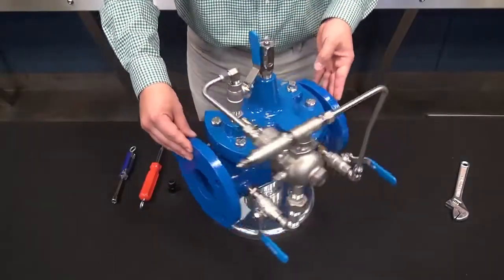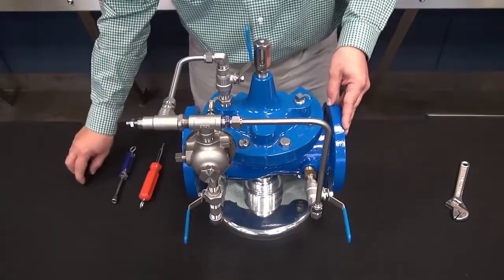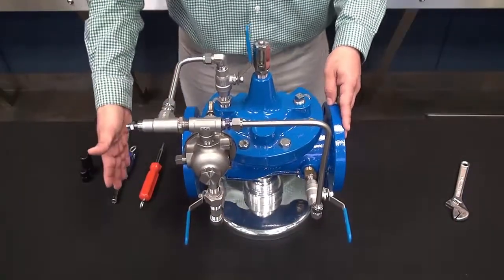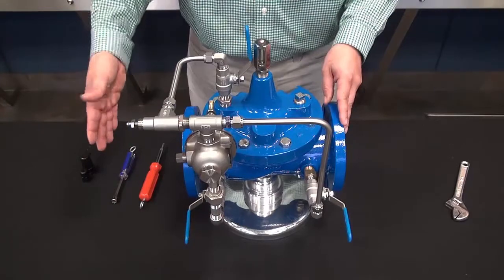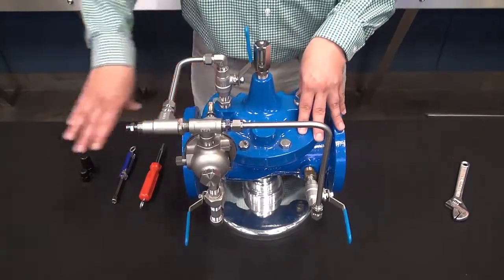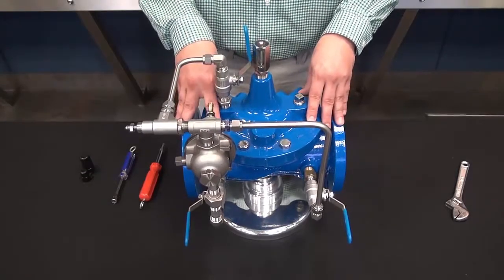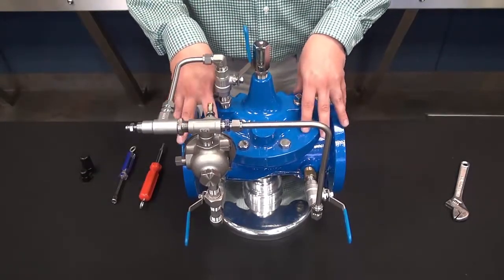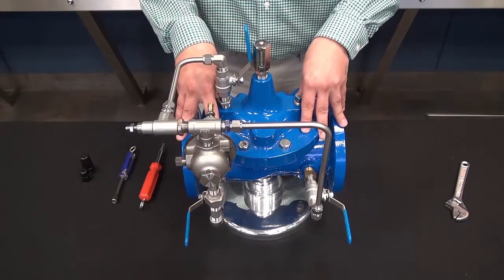Now that we know that we're at the lowest setting of the CRD, what we'll do at this point is we will slowly start to open up our downstream gate valve so that the main valve will open and start to introduce water into the system.